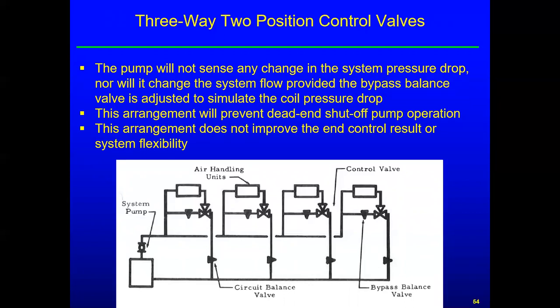Pump will not sense any change in system pressure drop, nor will it change the system flow, provided the bypass balance valve is adjusted to simulate the coil pressure drop. So that little valve on the bypass lines, if you can see my arrow, these little carrots on the bypass line, that's adjustable, and the balance people set it up to maintain the same pressure drop as the coils. So the pump doesn't see any change as these things switch from coil flow to bypass flow.